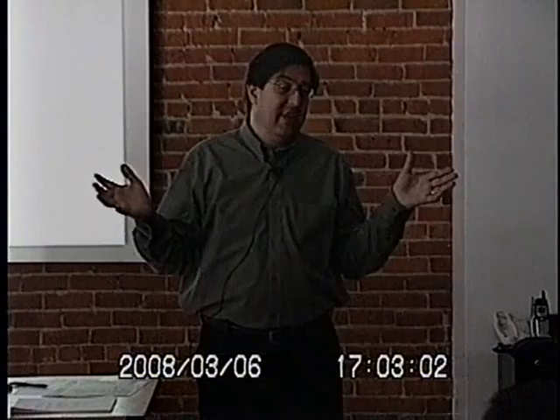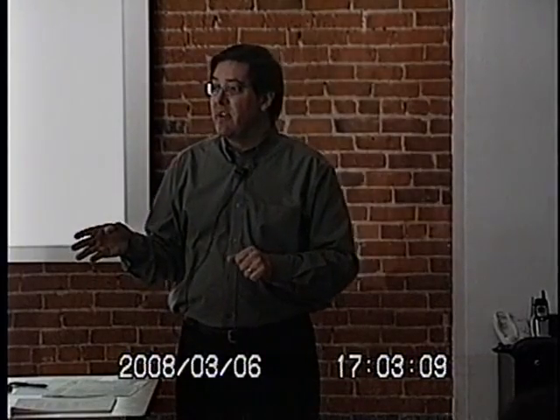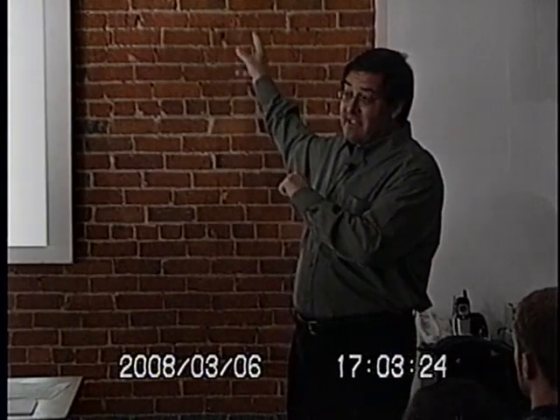One or the other. I've got a building I'm working on right now that we have not resolved the issue on yet. It's a phone switch. It's all it is in that building. There aren't even any people in there. And they told me that they have 10 tons of cooling units in there that last summer they claim were running wide open and there's no more capacity. So I went in and felt the phone switches and looked up the nameplate rating and looked at the meter readings, and I checked a site in Germany that has the same phone switch in it from Northern Telecom just to see if I was out of my mind. It's 12.5 kilowatts of phone switch in there. 12.5 kilowatts should take 1.5 or maybe 2 tons on a hot day to cool it. And they're telling me 10 tons is running wide open to keep this building cool.